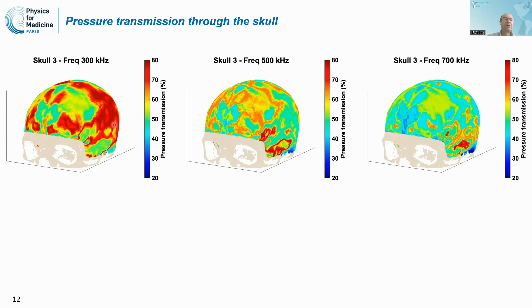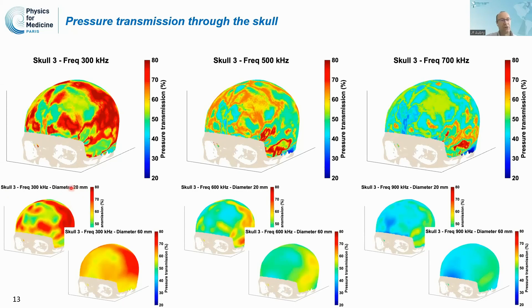This is the transmission in percentage through the skull for three different frequencies, showing a very heterogeneous transmission of the ultrasound. Since transducers have a given diameter, we also show the averaging effect of using either a 20 mm or a 60 mm diameter transducer. For the same skull, you can see the impact on transmission when accounting for both frequency and transducer size.